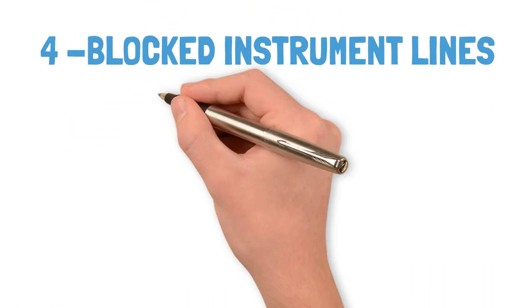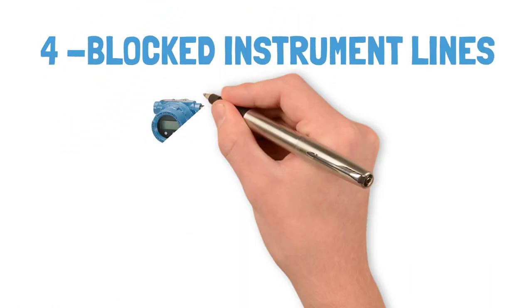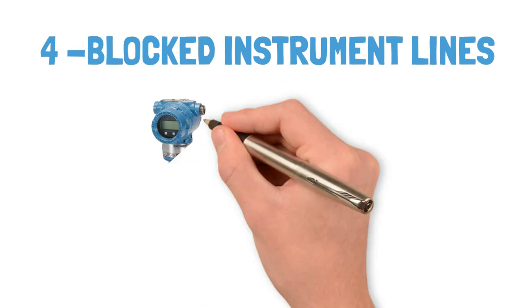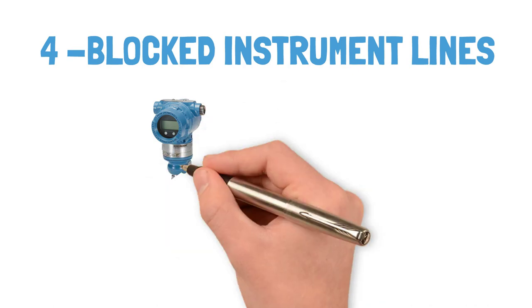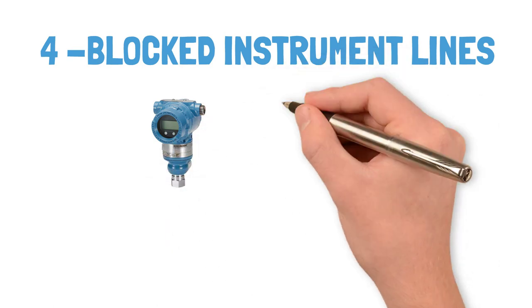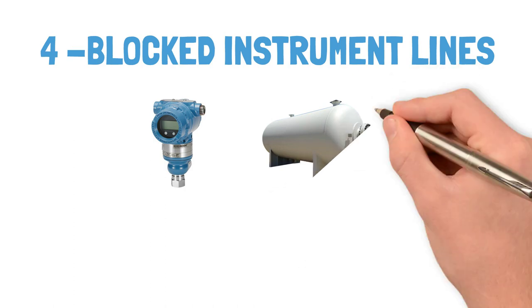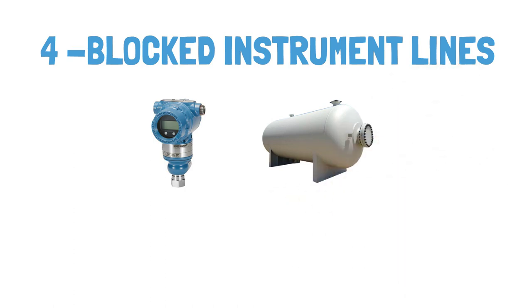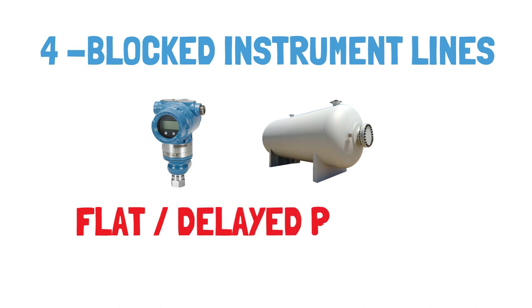Blocked instrument impulse lines. If there is any blockage between the instrument and the process it is measuring, this could cause flat or delayed readings. This will depend on the type of instrument you are working on, but always keep in mind this failure mode, especially on liquid processes that might contain particulates.